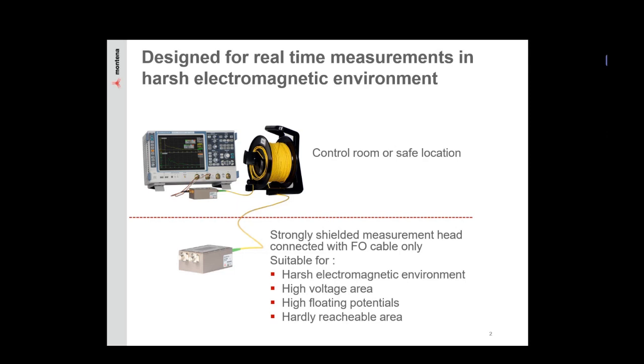So we're going to talk today about the Montena Fiber Optic Links. They've been designed for real-time measurements in harsh electromagnetic environments. Basically they're strongly shielded, a measurement head or transmitter connected with a fiber optic cable, suitable for harsh electromagnetic environments, high-powered electromagnetics, high-powered fields, high voltage areas, and areas that are hard to reach, for example the top of a radiating line or an antenna tower where you want a sensor. These can be placed in a small form factor in hard to reach locations, because we have a method of remote controlling them in terms of power and configuration.